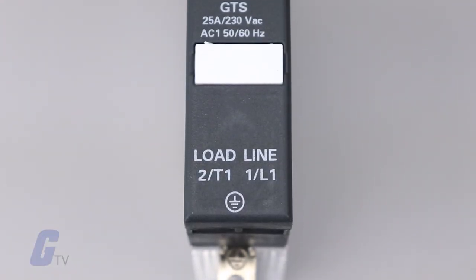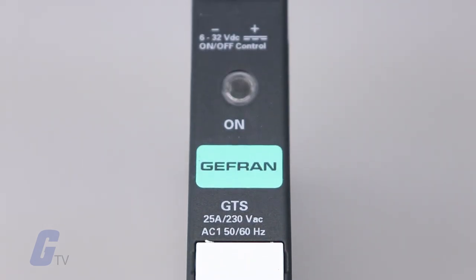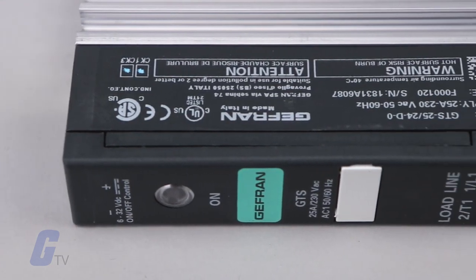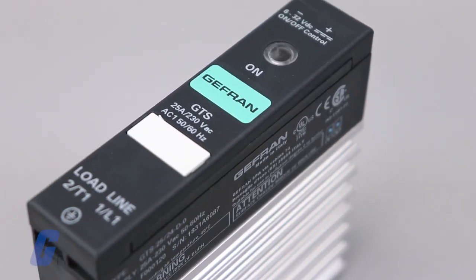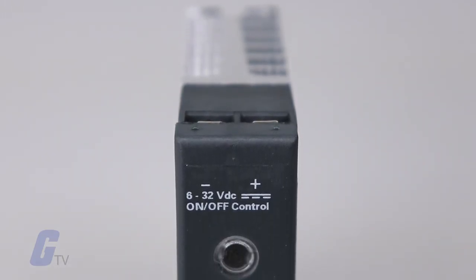The Gefran GTS series offers a range of solid state relay units with current ratings between 10 amps and 120 amps and nominal voltages of 230 volts AC and 480 volts AC. According to the type of load, there are Triac versions and double SCR versions. All models have been designed to guarantee continuous operation at the full current rating and an ambient temperature of up to 40 degrees Celsius.